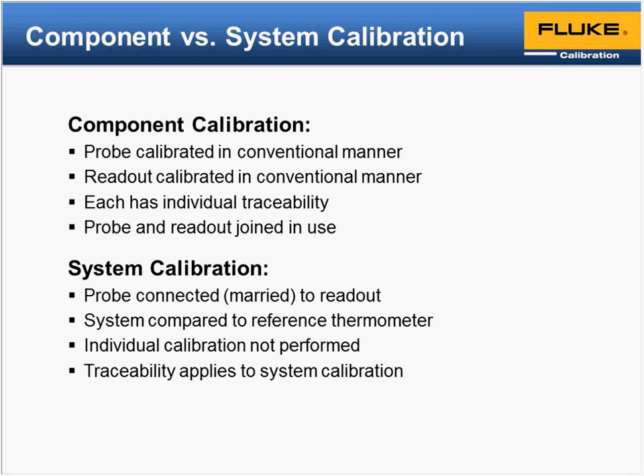So once you do a system calibration, these two pieces are locked together. We're not splitting them apart and taking a hard look at each one. What typically happens in a system calibration is any error that's being contributed through the probe piece gets sorted out on the electronic side of the readout piece. You just have this one link that we've calibrated across the board. So again, if you had multiple probes that you use in different applications, the traceability would apply to both pieces in that particular case.